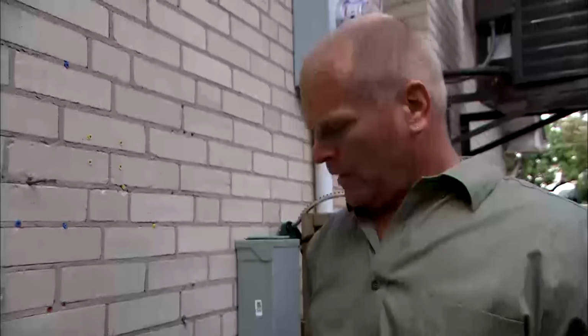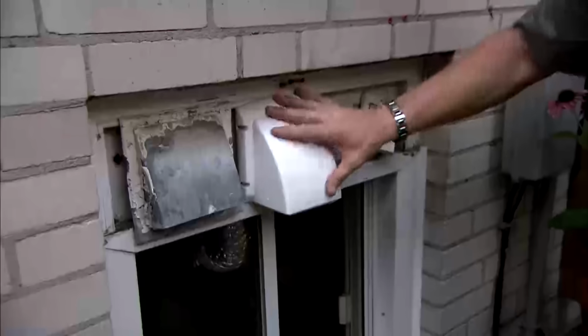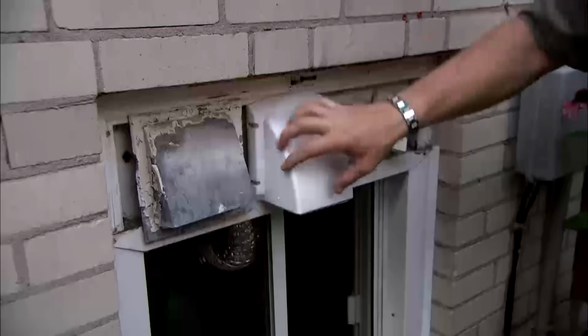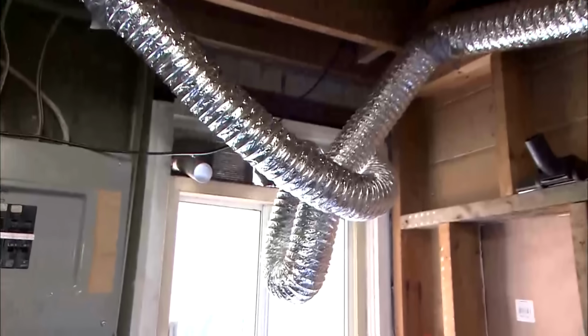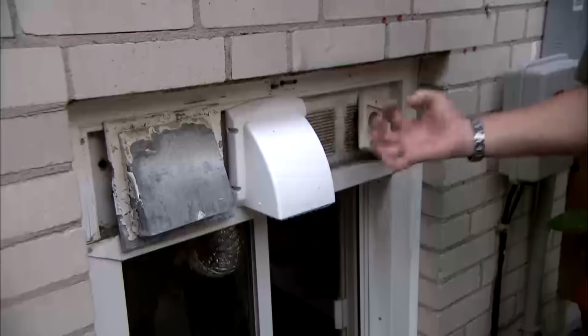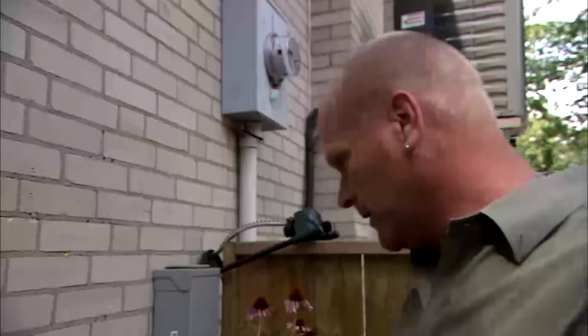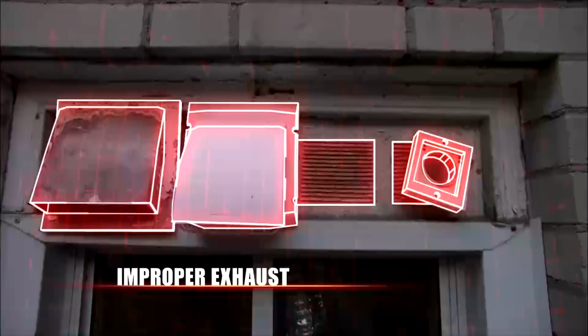Here's something clear as day. I'll bet it was freezing cold in this room in the winter. Why? Cold air rushes into improper exhaust lines. These are correct, it's just the lines that run to them. Cold air rushes in here, cools that zone, cools the floor. Should have caught this, should have said something in the report. Something's fishy here, I don't know what it is, but it's wrong.